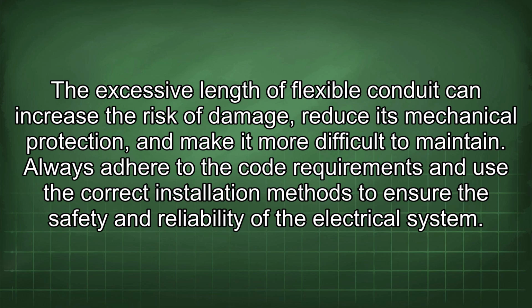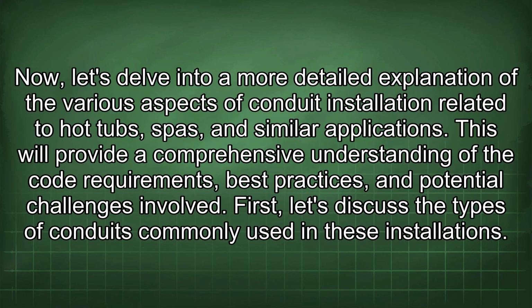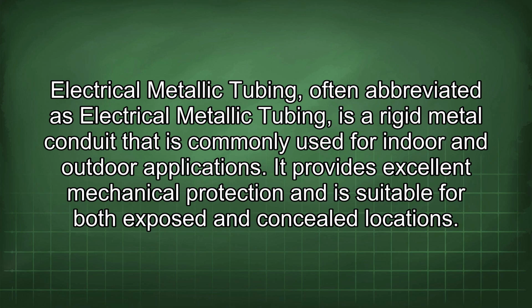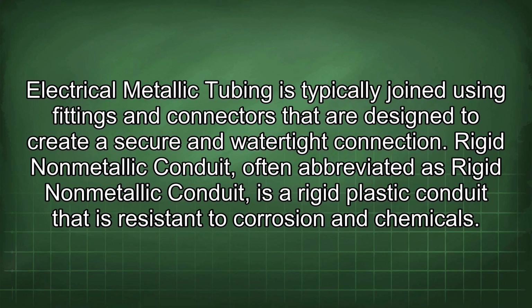Now let's delve into a more detailed explanation of the various aspects of conduit installation related to hot tubs, spas, and similar applications. This will provide a comprehensive understanding of the code requirements, best practices, and potential challenges involved. First, let's discuss the types of conduits commonly used in these installations. Electrical metallic tubing, often abbreviated as EMT, is a rigid metal conduit that is commonly used for indoor and outdoor applications. It provides excellent mechanical protection and is suitable for both exposed and concealed locations. Electrical metallic tubing is typically joined using fittings and connectors that are designed to create a secure and watertight connection.